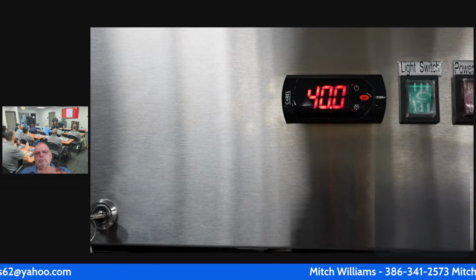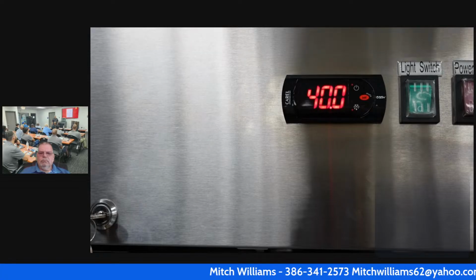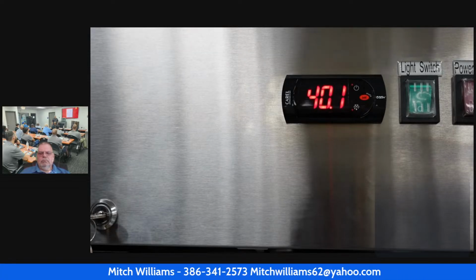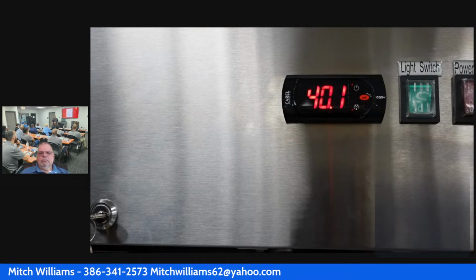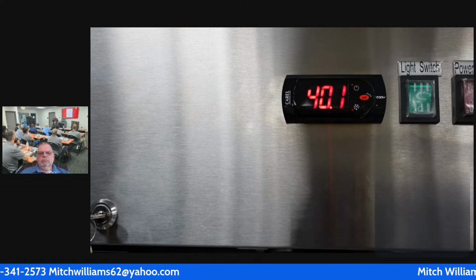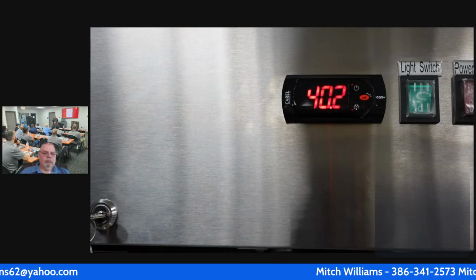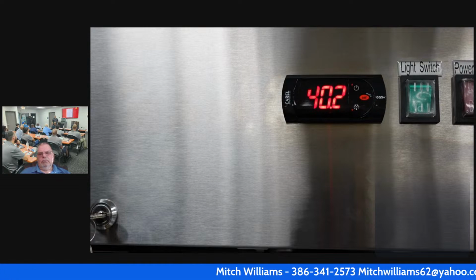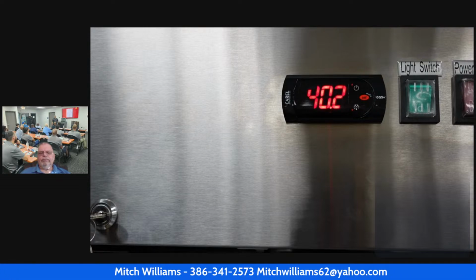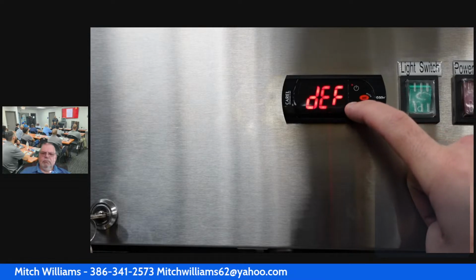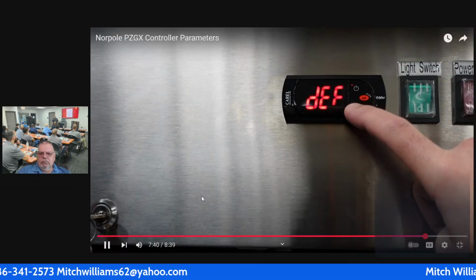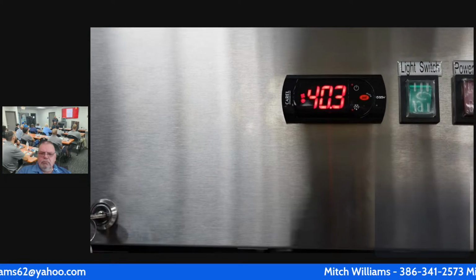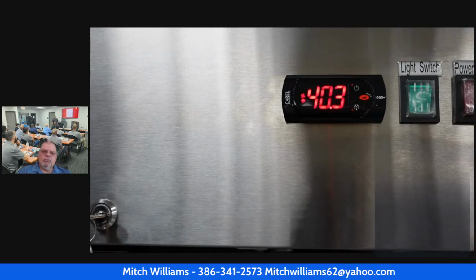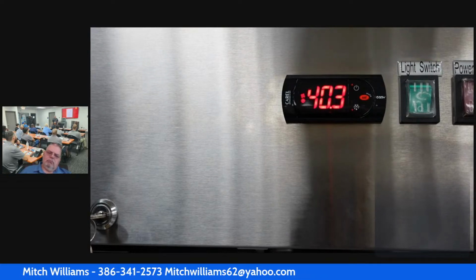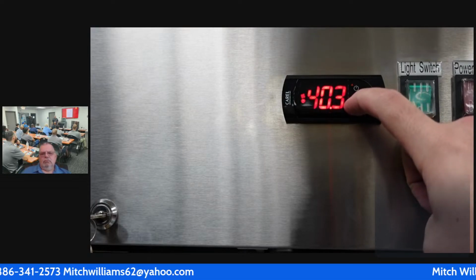One more thing to note is that you could force the unit in and out of a defrost. If you noticed any frost or ice building up near the evaporator fans, and that could be caused by leaving the door open, you can force the unit into a defrost. In order to do that, go ahead and press and hold down the bottom arrow for 3 seconds. You'll see DEF displayed on the screen, and then you'll have a little defrost icon. You could also force the unit out of a defrost. In order to force it out of a defrost, go ahead and repeat that same operation.